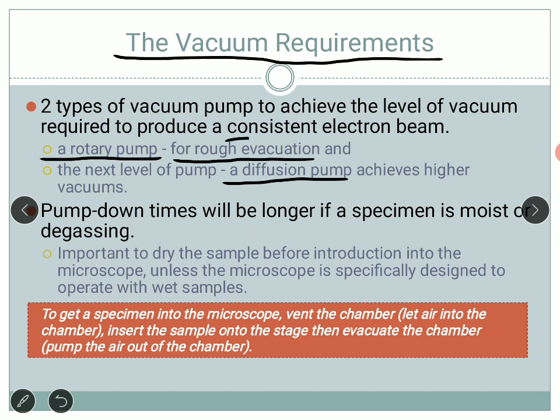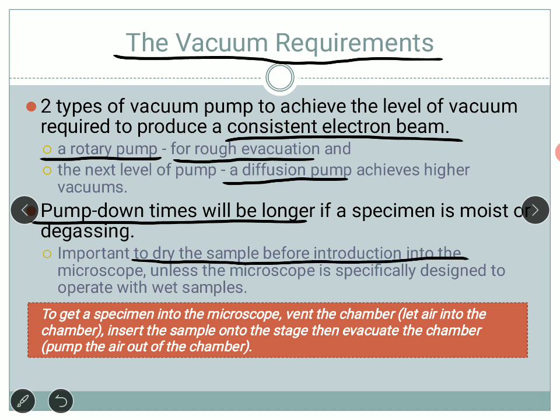This is very important for producing a consistent electron beam. The pumping time is important because if the sample is moist, the pump time can be longer — it will take longer to pump out all the air from the system. We need a sample which is completely dry. However, if you are studying wet samples such as biological samples, the microscope design itself is different. An environmental scanning electron microscope can read wet or biological samples.